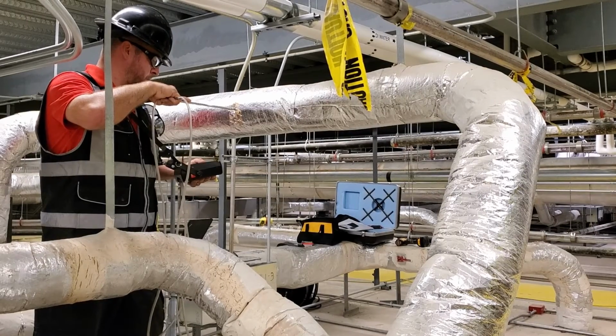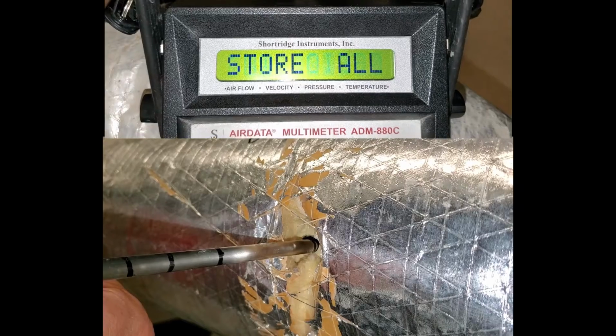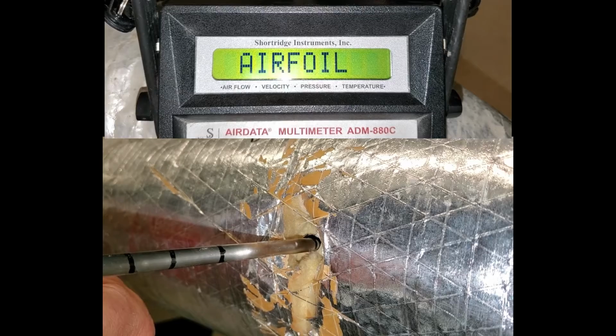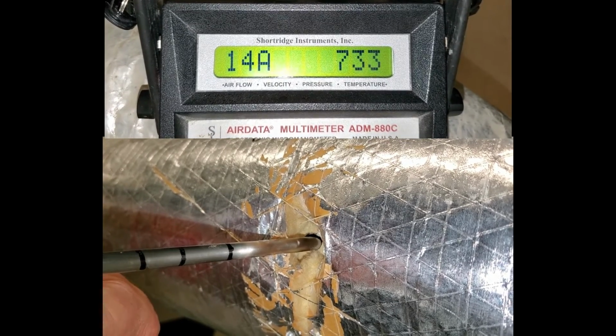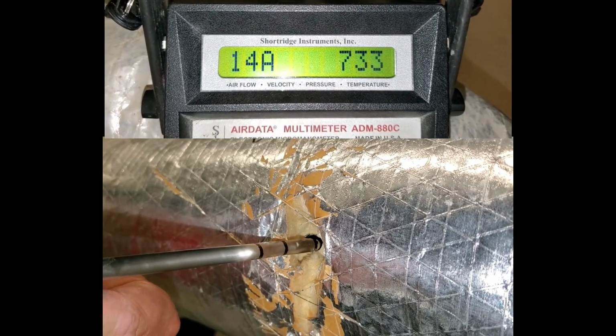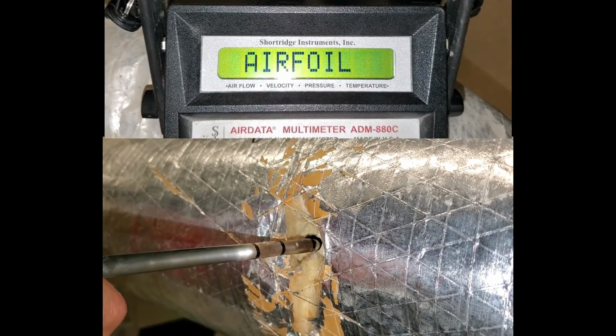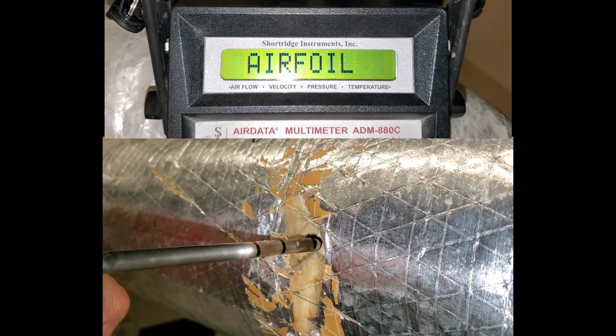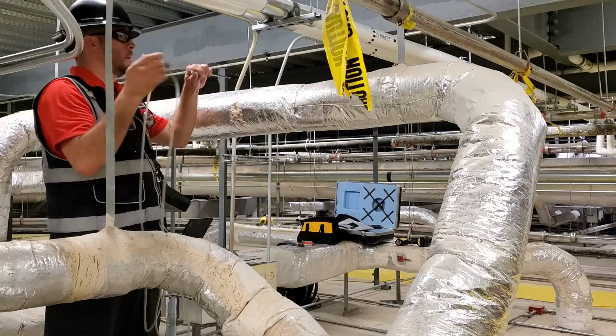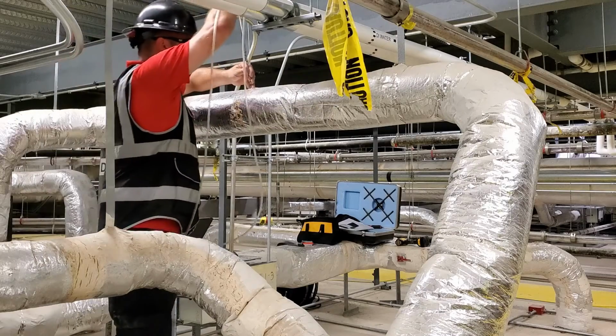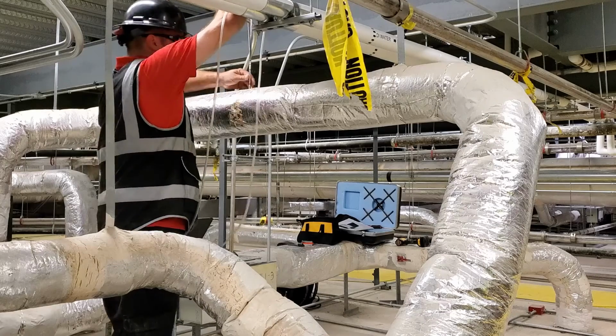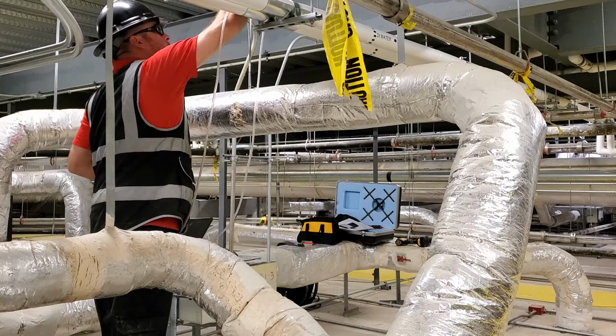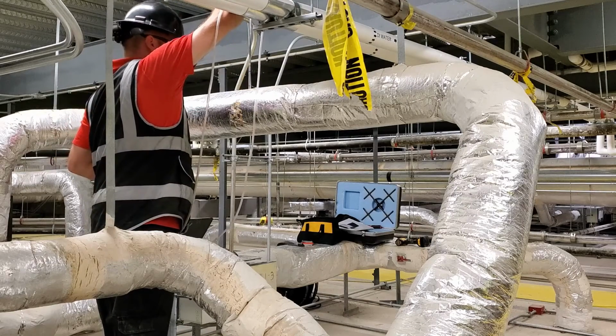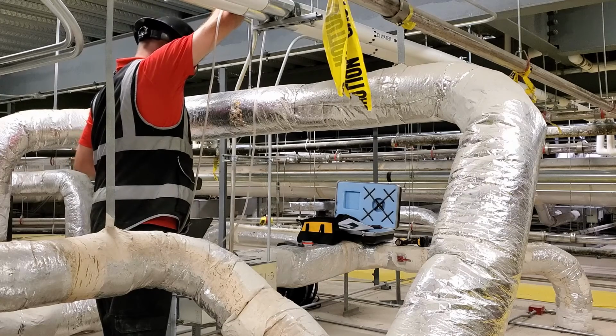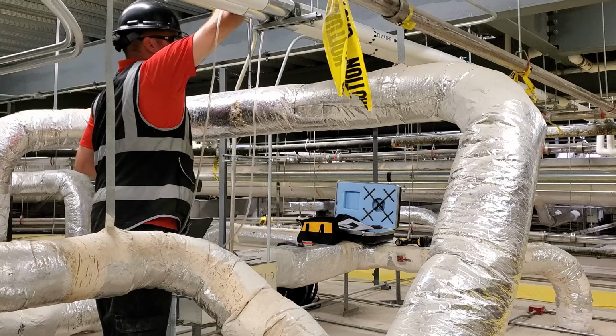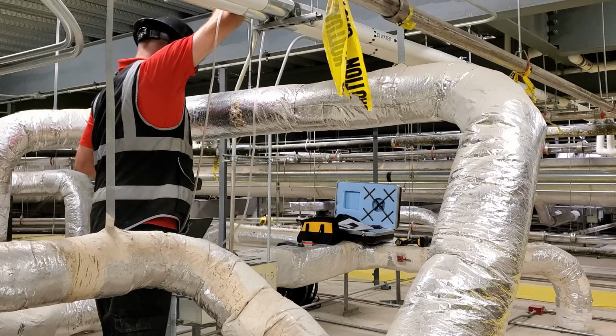Anyways, and so then we'll just show you a quick little close-up of what's actually going on. So as you can see, he's just aligning those marks with the edge of the hole, and then clicking read, and then it gives him a velocity, and later you'll average all those velocities and calculate a CFM. You multiply the velocity times the area of the duct, which for a 6-inch is 0.2 square feet, and then you'll get a CFM from it.